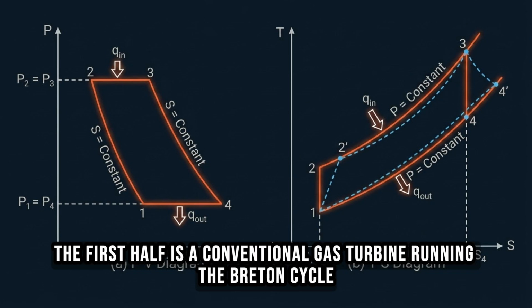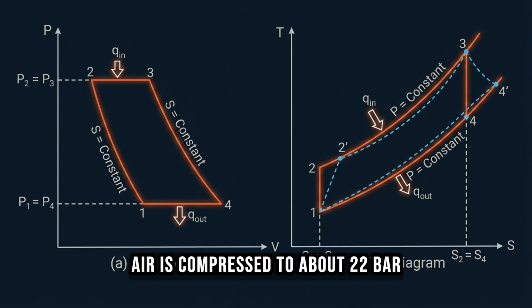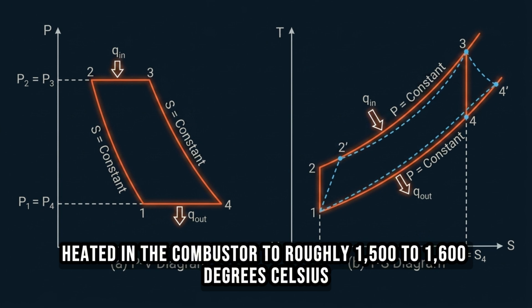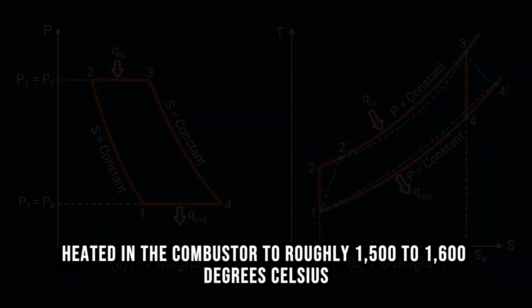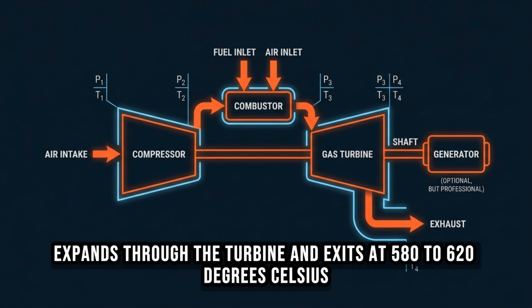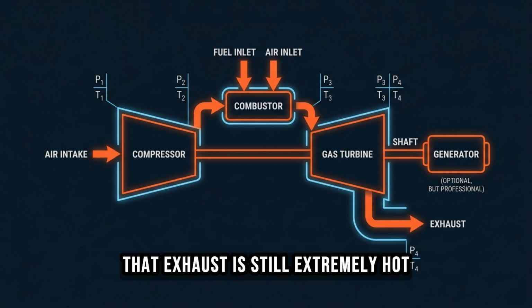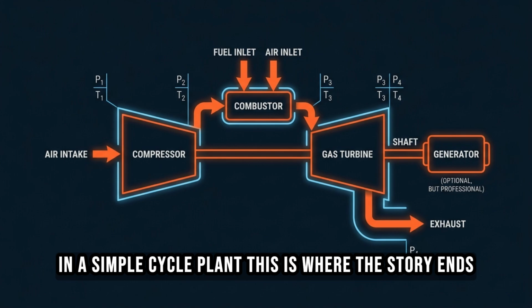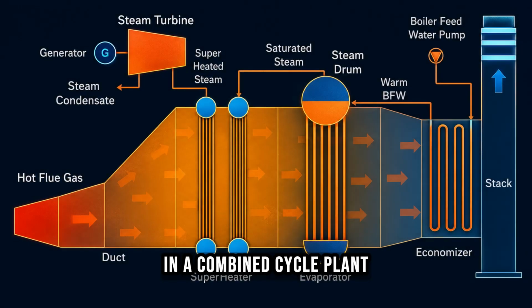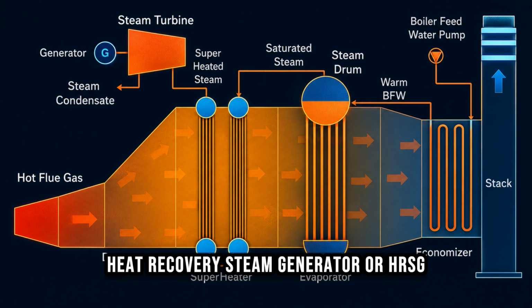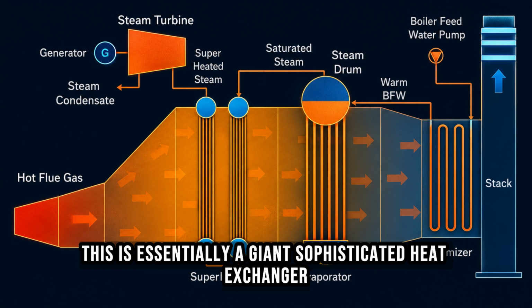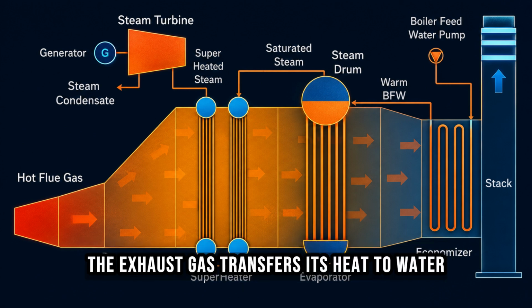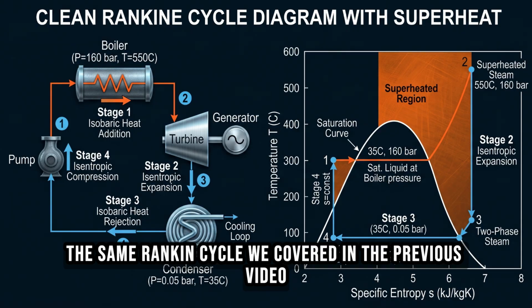The first half is a conventional gas turbine running the Brayton cycle. Air is compressed to about 22 bar, heated in the combustor to roughly 1,500 to 1,600 degrees Celsius, expands through the turbine, and exits at 580 to 620 degrees Celsius. That exhaust is still extremely hot. In a simple cycle plant, this is where the story ends. In a combined cycle plant, that hot exhaust goes into a heat recovery steam generator, or HRSG. This is essentially a giant, sophisticated heat exchanger. The exhaust gas transfers its heat to water, generating steam that drives a second turbine. The same Rankine cycle we covered in the previous video.